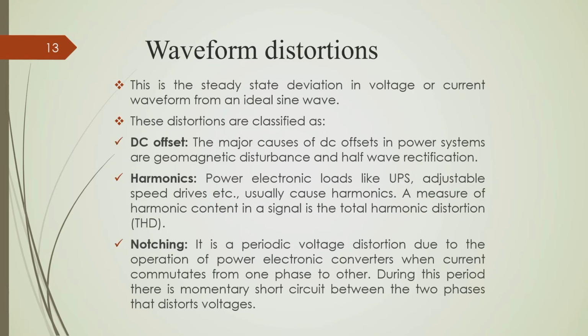Now, we also have some voltage quality problems which are called waveform distortions. So, what are the different types of waveform distortions we have? As we said, one is DC offset, that means presence of DC voltage in the sinusoidal supply voltage, which is another reason for waveform distortion. Also harmonics. Harmonics are basically a periodic type of voltage distortion. Okay, I will come to that.